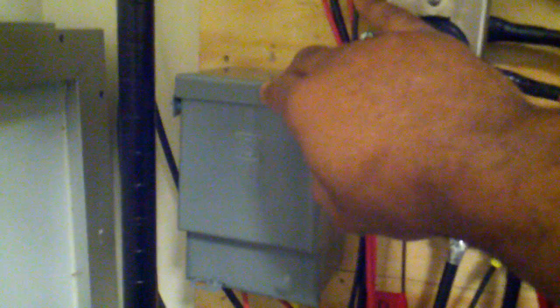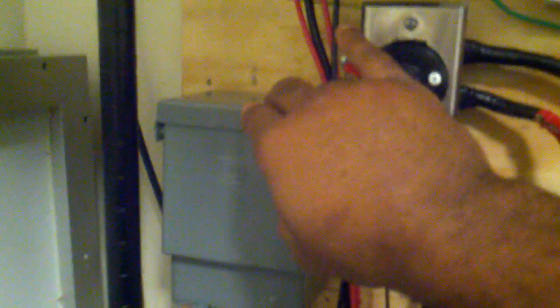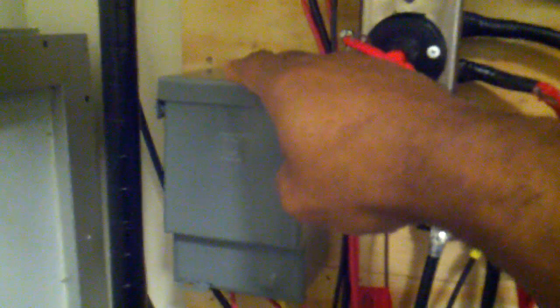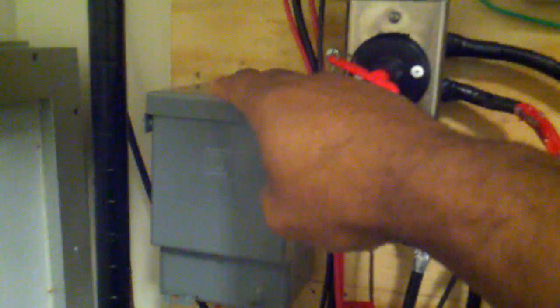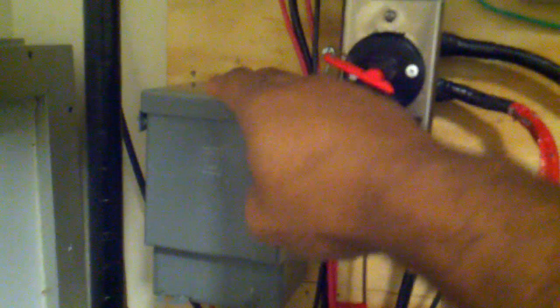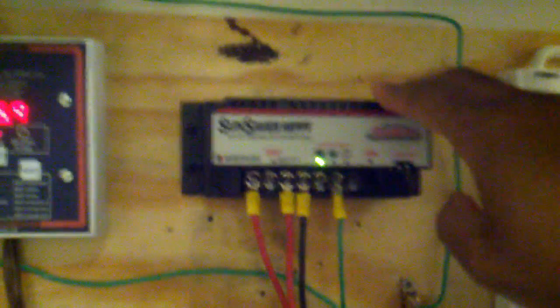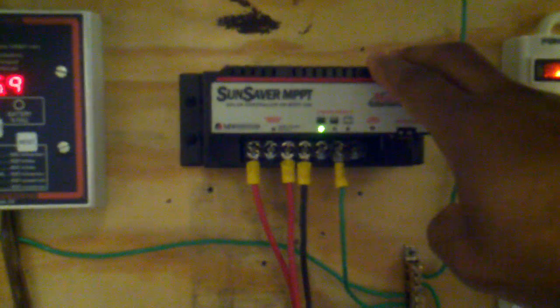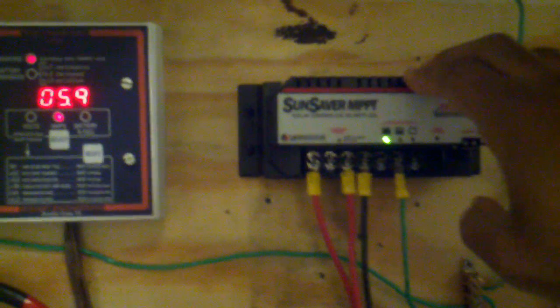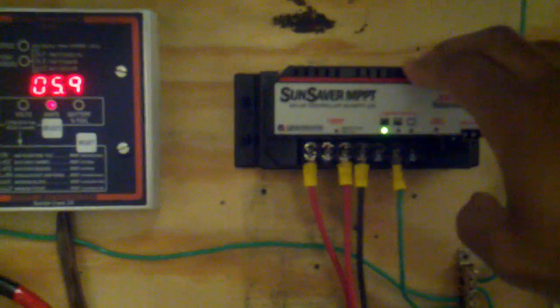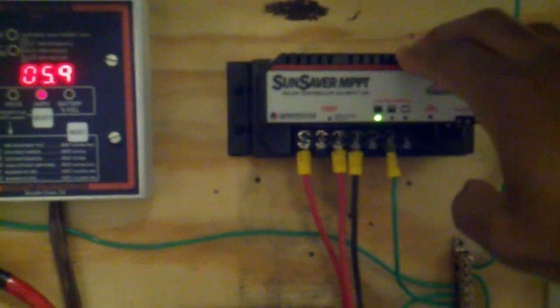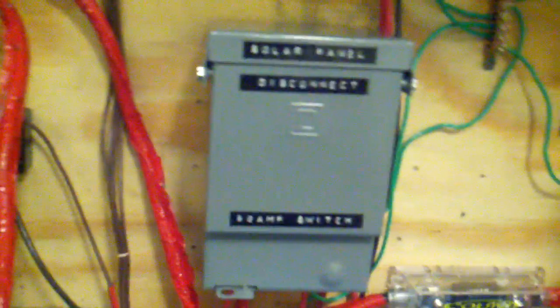This, I need to get it labeled. I ran out of labeling material right at the last minute. But this is a disconnect from the chargers to the battery. This is a disconnect from there. Each one of these is 60 amps. The key thing is, there's not going to be more than 15 amps coming from either one of these controllers to the battery at any given time. And there's not going to be more than 8 amps from the panels to the chargers at any given time. So, these switches should be more than adequate. If I find that they're not, then obviously I'll replace them.